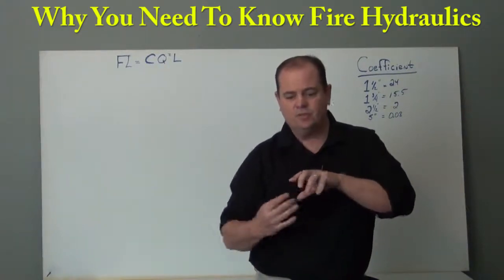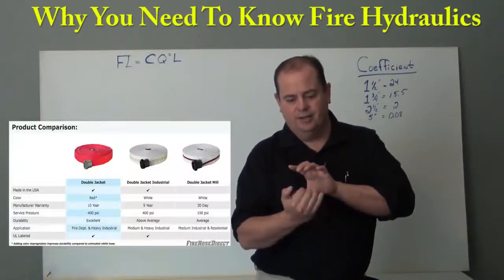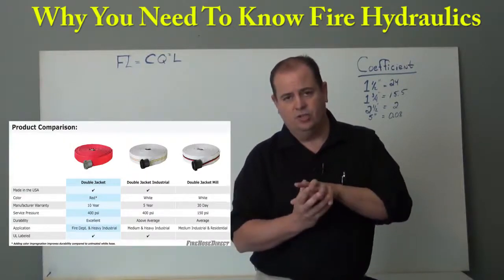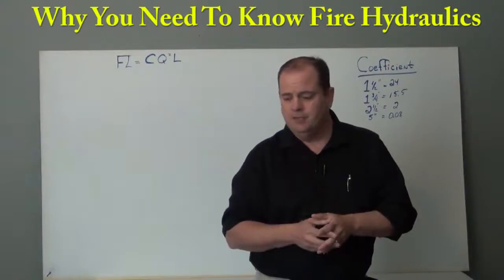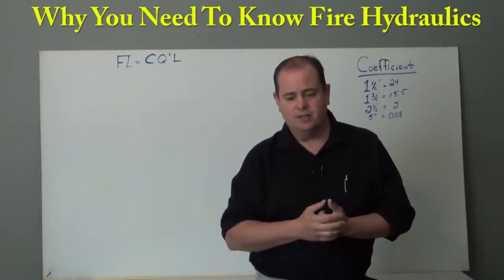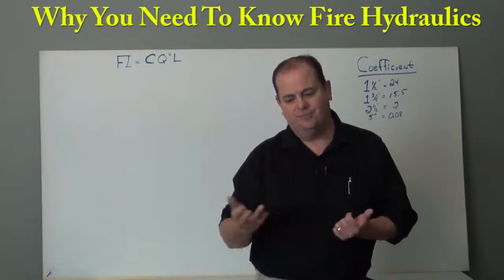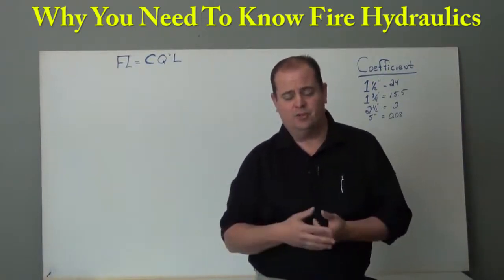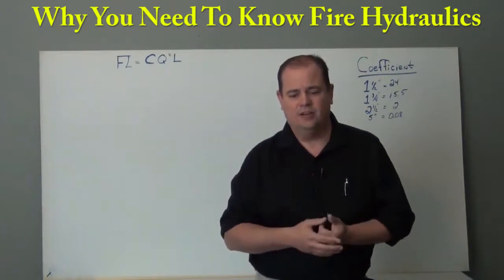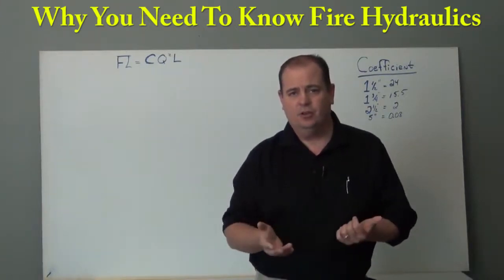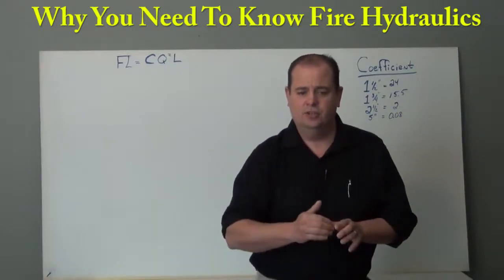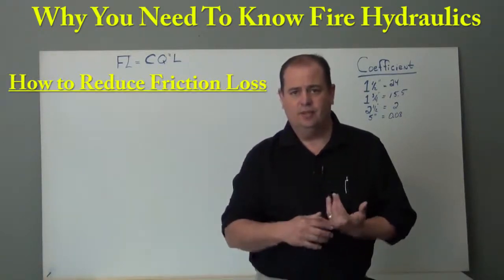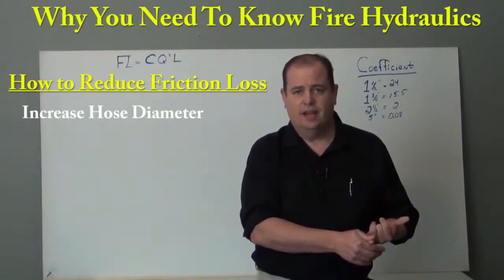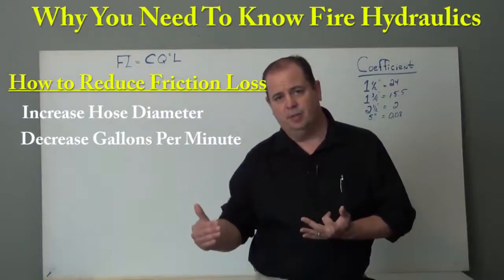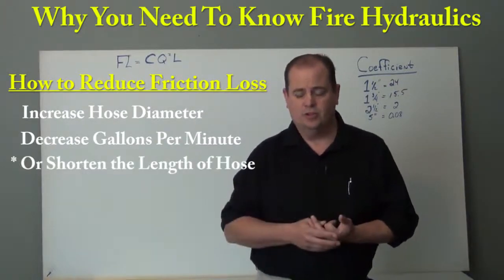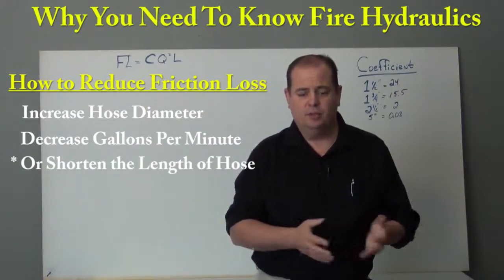If you look at your hoses, they have a pressure rating set on them for what they're tested at, and you want to make sure you're not pushing close to that, because the hoses could fail. So where I'm going with this is, whenever you're speccing a truck out, say you're speccing a 185 gallon per minute nozzle, you're putting 400 feet of hose on it, and you're thinking, hey, why not throw another 200? Do the equations, and you figure out you're pushing the limits, you're exceeding that. So what you could do is one of two things: either increase the diameter of the hose or drop the gallons per minute down. This is the reason why the equations are pretty beneficial in helping you spec out a truck.